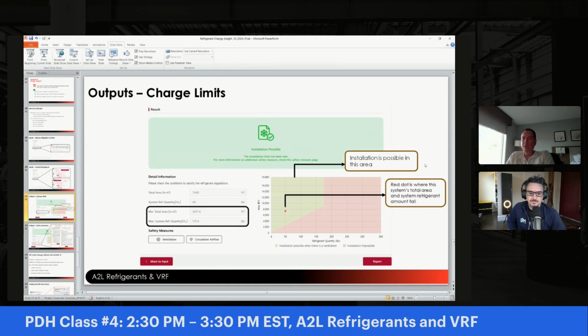When ventilation is selected as one of your mitigation controls, the releasable charge is actually the system charge, since in this particular example there's no shutoff valve used. So your total area is calculated by adding the current room and the connected room together for ventilation. And since this total area is larger than the minimum required total area, this installation is possible.